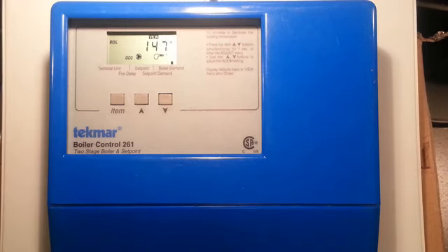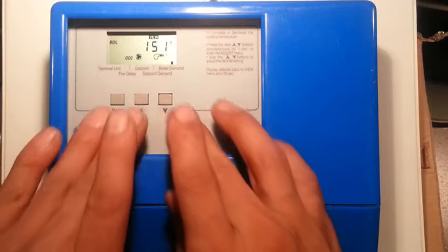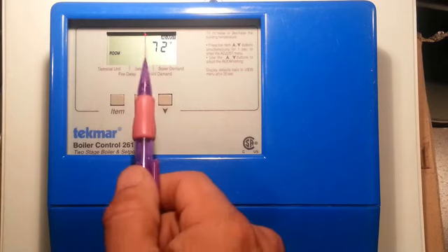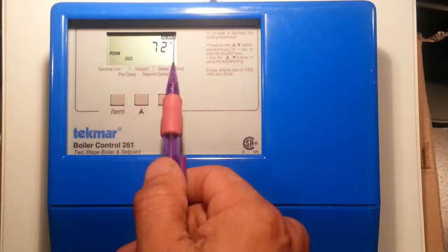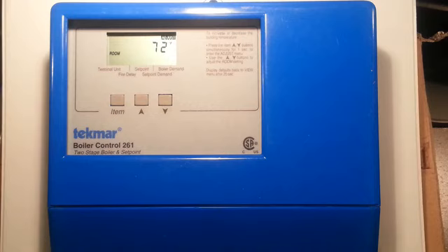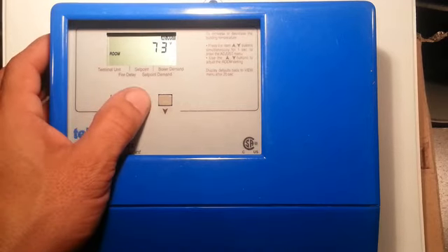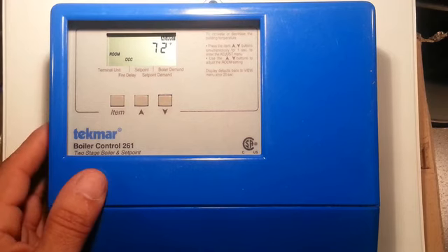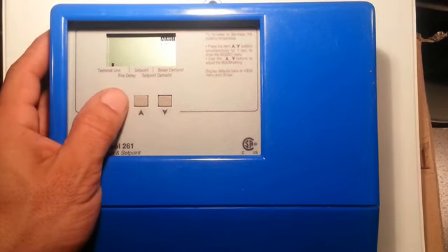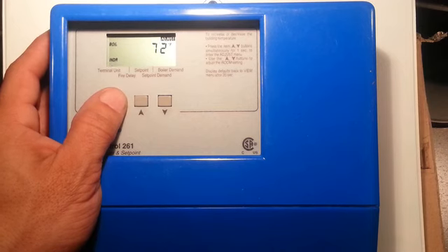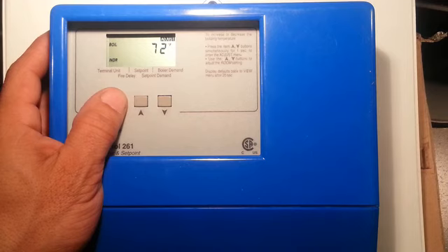If you wanted to change the settings on this control, once again, push all three buttons at the same time, and then it switches from what was previously said view, it moves to adjust, and it's flashing room OCC, which tells us that's the room occupied setting. This setting and the corresponding boiler indoor temperature are set at the same set point.